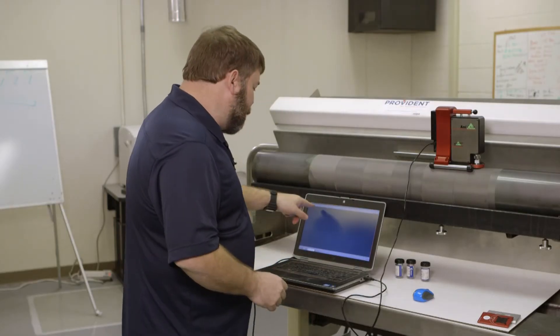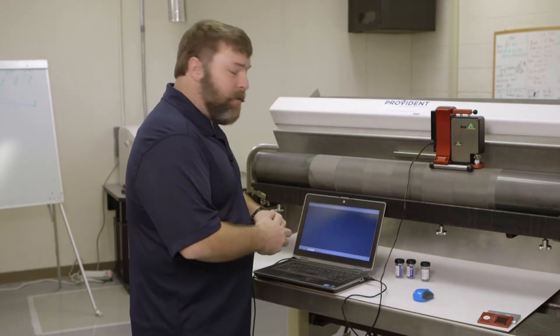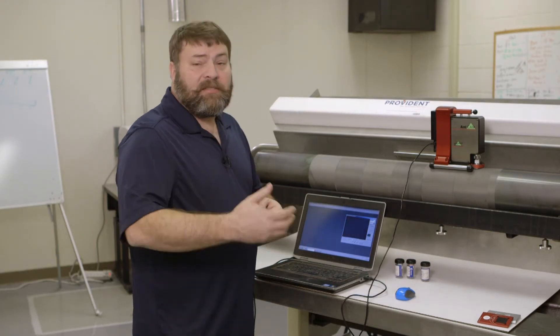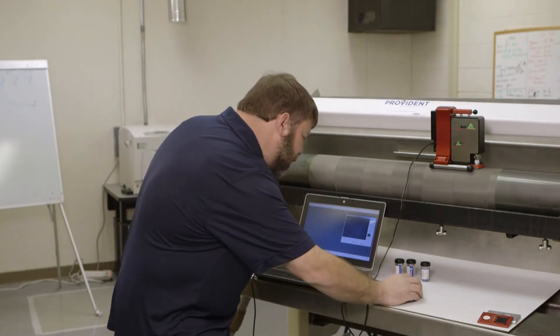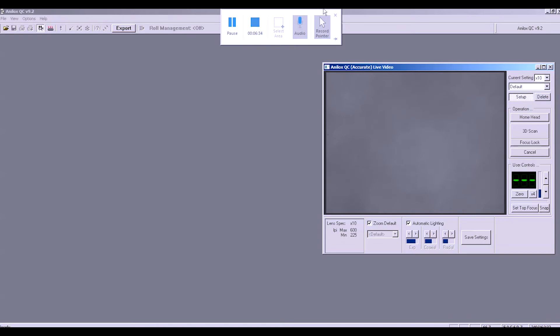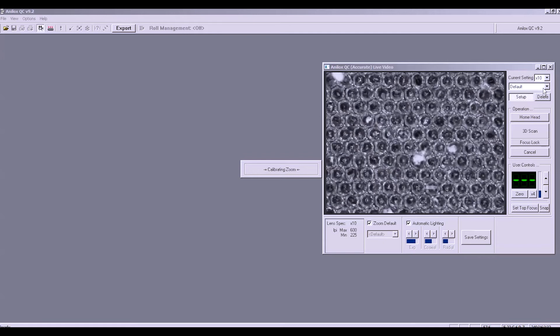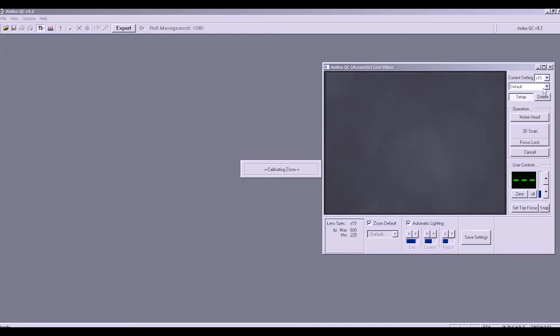Once it's in position, I have my Anilox QC program started here. I'm going to start the video feed and then I just need to make sure that the video feed has the correct lens chosen. So I'm going to choose the 10 power lens. And it's automatically homing the head, which is a rough adjustment. So I'm going to let it do its rough adjustment. Once this box goes away, we should be able to see the anilox roll.